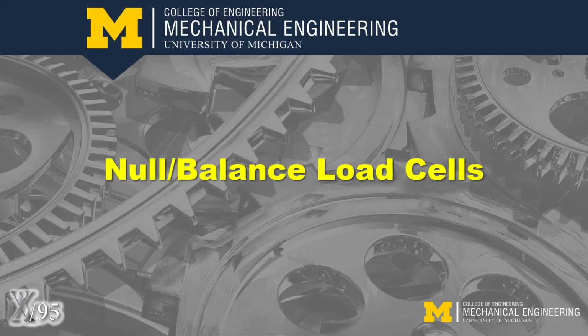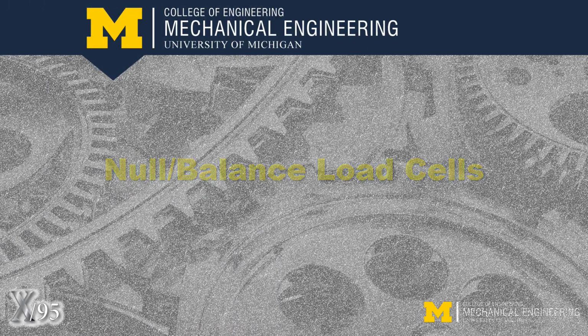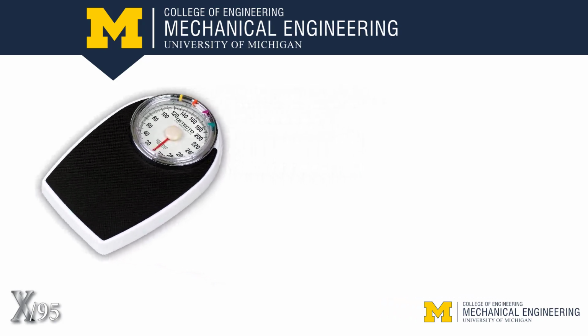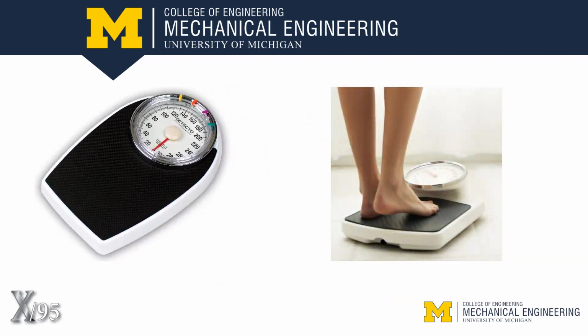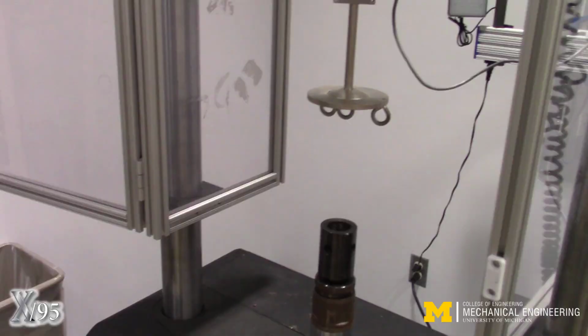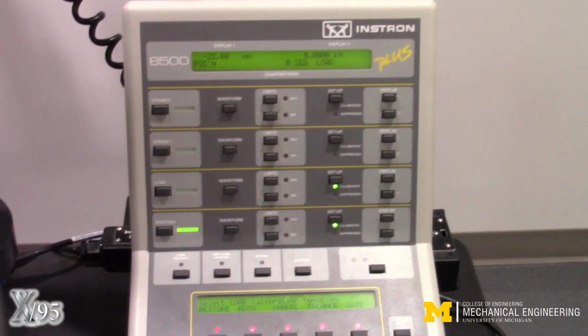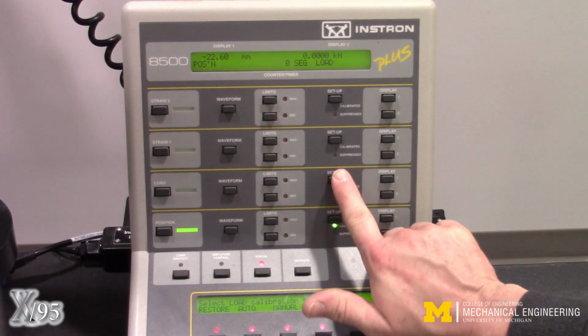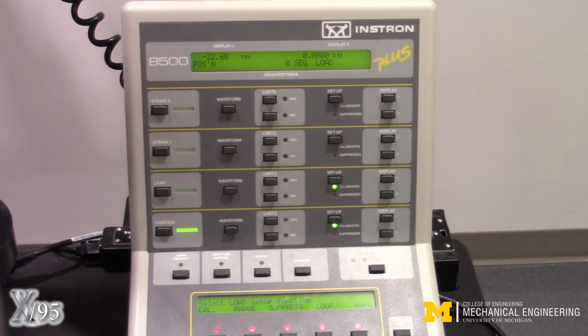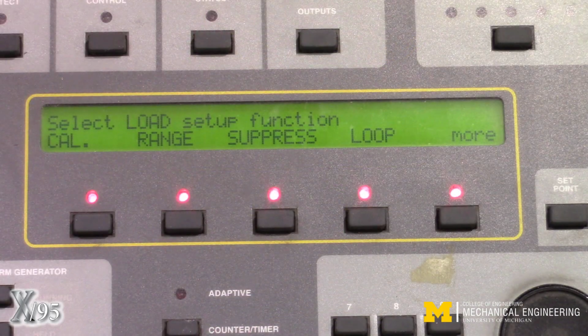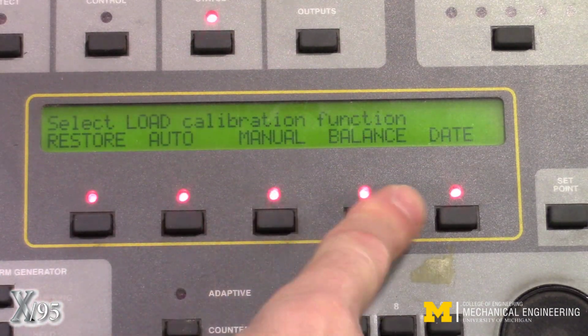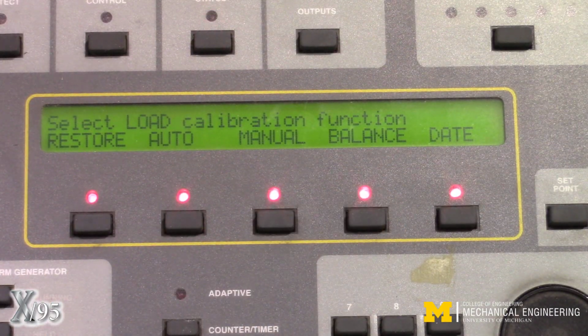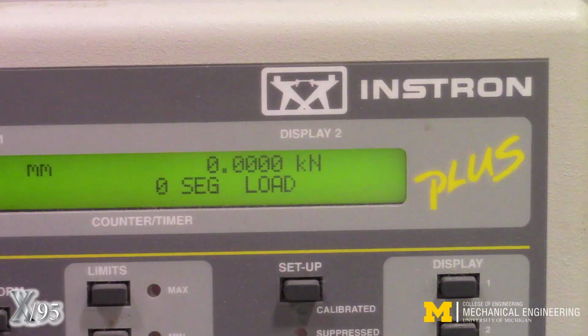Before we begin, you must balance or null the load cells, which is comparable to zeroing out your bathroom scale before weighing yourself. As such, the load cell should be completely unloaded. On the upper console of the Instron, press the Load Setup button. Moving to the lower console, press the soft key sequence Cal, and Balance. After a few seconds, the load display should read 0.